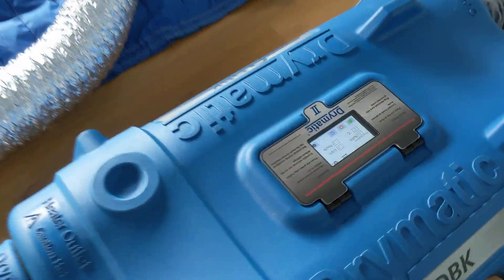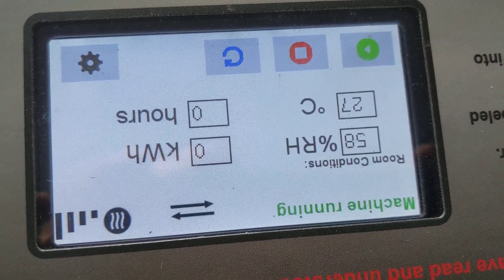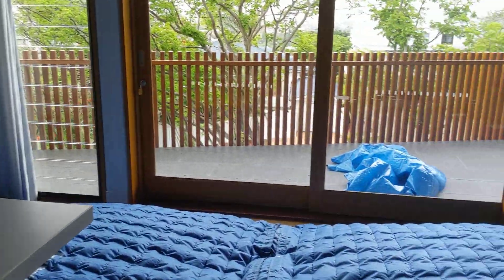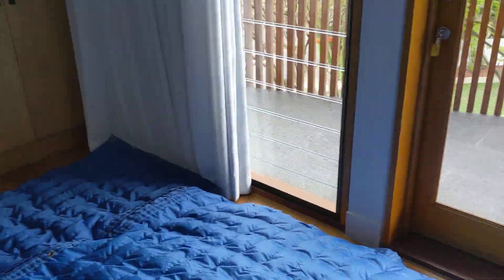This screen here — that's what we're starting with: 58 RH and 27 degrees. We want to heat this up to about 40 degrees. It's been leaking through these doors, so it's an insurance claim for the builder.